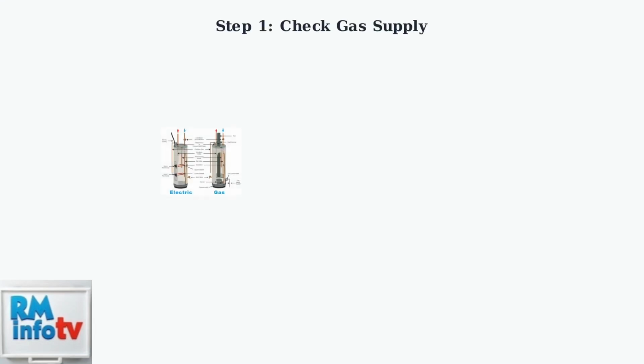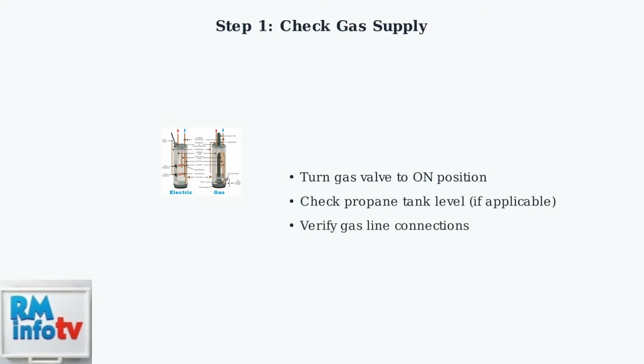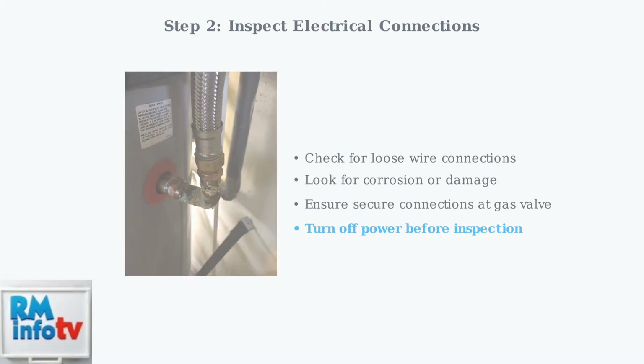When your Rheem water heater shows a flashing blue light, follow these systematic troubleshooting steps to identify and resolve the issue. Step 1. Check your gas supply. Ensure the gas valve is turned on and your water heater is receiving gas. For propane users, verify your tank level is adequate. Step 2. Inspect all electrical connections. Look for loose, corroded, or damaged wires, particularly at the gas control valve and thermostat connections.